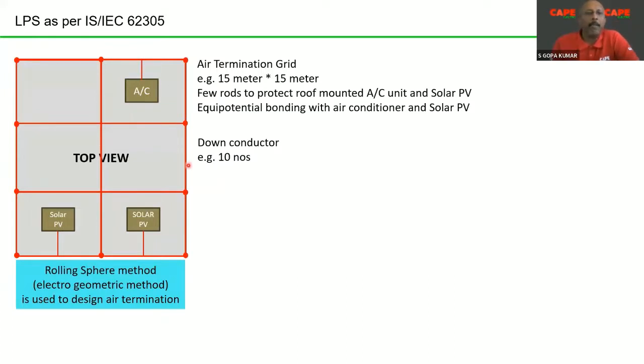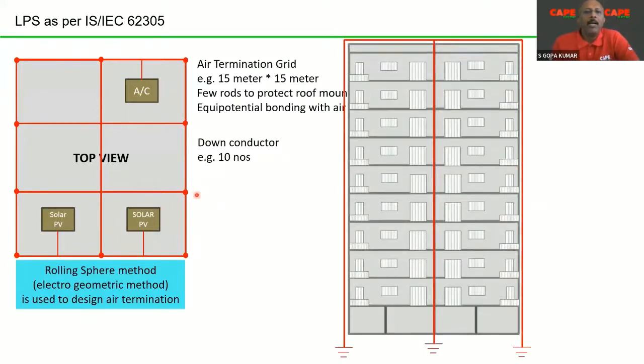Say, for example, maximum 10 meter, or an average 10 meter between down conductors. So in this typical case, we have, let us say, 10 down conductors. You can see the building at the top, there is a mesh and there are 10 down conductors, and each of the down conductors has to be connected to an earth termination system.